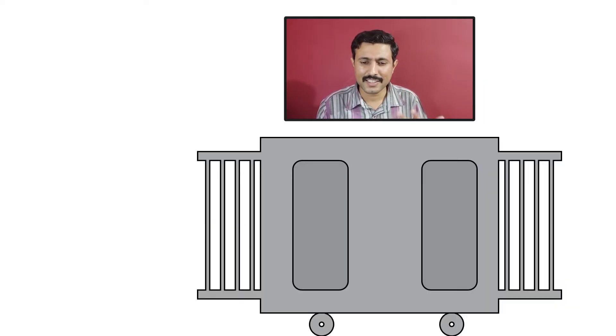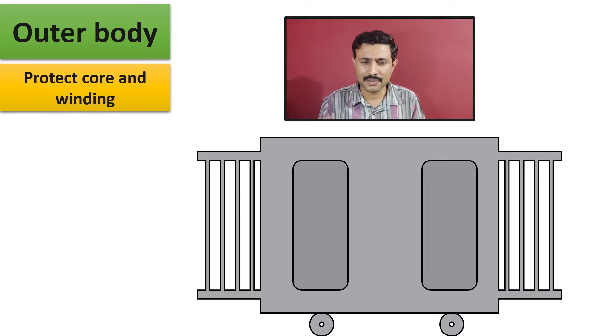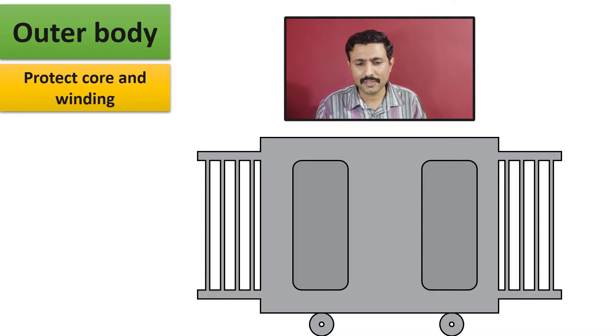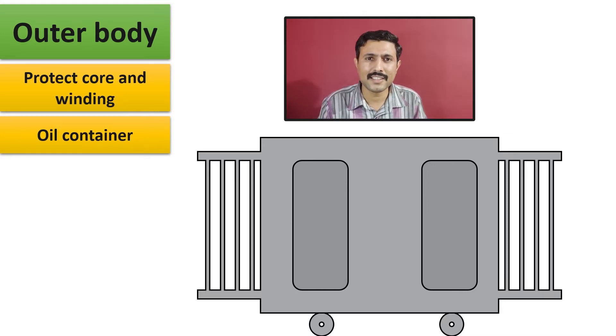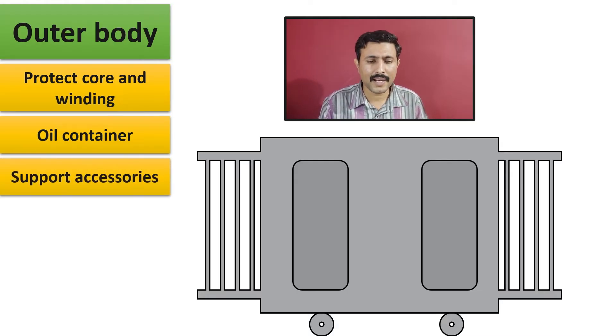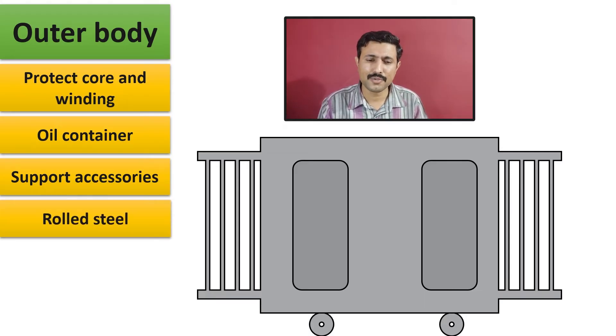The outside of transformer is its body, known as the outer body of transformer. This outer body is used to protect the core and winding from outer conditions. Another purpose of this outer body is to behave as a transformer oil container, because all the transformer winding and its core is submerged in oil placed inside this outer body. One more use of this outer body is to provide support for all the accessories. This outer body is constructed of rolled steel material to provide strength.